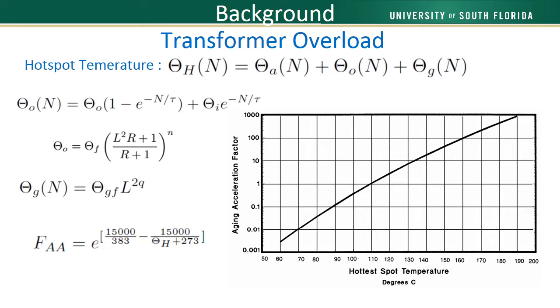Generally, the conductor or insulation material is the hottest spot of a transformer, whose temperature cannot be measured directly. So the hotspot temperature theta H of a transformer at time n is the summation of ambient temperature theta A, top oil temperature rise over ambient theta O, and hotspot temperature rise over top oil temperature theta G. Both theta O and theta Z only depend on loading L for any specific transformer. The graph shows the aging acceleration factor FAA in log scale for theta H. It means if the hotspot temperature of a transformer is 110 degrees Celsius for 1 hour, it will lose 1 hour of effective life. But if the hotspot temperature is 130 degrees Celsius, then it will lose 10 hours of life, whereas for a hotspot of 90 degrees Celsius, it will lose only 0.1 hour of effective life.